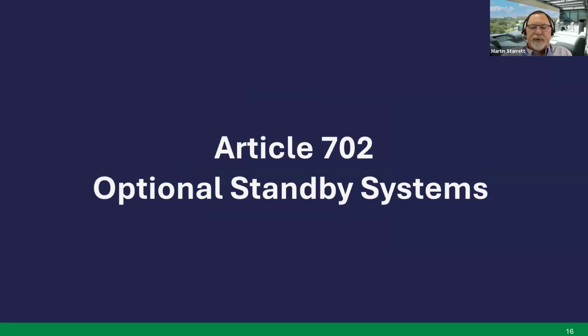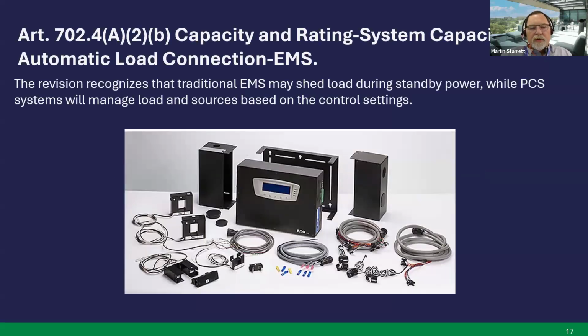Article 702, optional standby systems. So Article 702.4A, 2B, capacity and rating, system capacity, automatic load connections for energy management systems. The revision recognizes that traditional energy management systems may shed load during standby power, while power control systems will manage load and sources based on the control settings. Next slide.